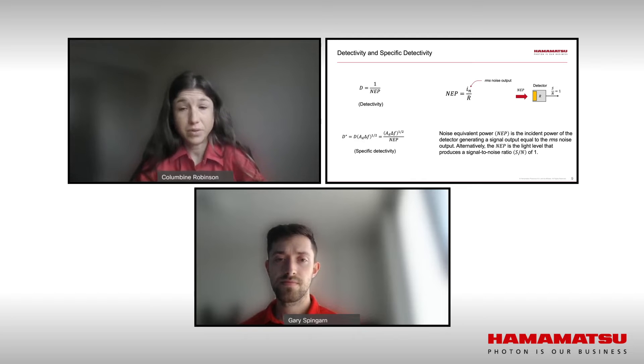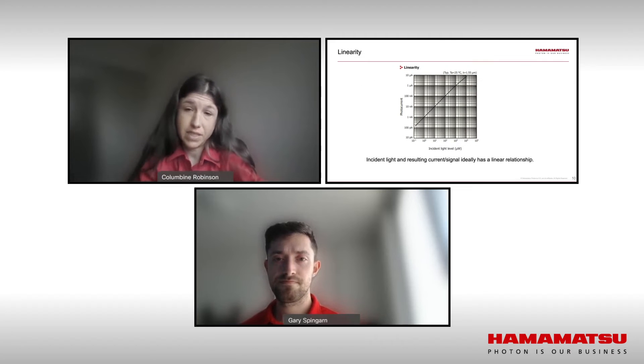NEP is the amount of signal required to achieve a signal-to-noise ratio of one. Ultimately you want as high of a signal-to-noise ratio as possible. D-star is the reciprocal of NEP, so the higher the value, the better. Now for linearity: when looking at the sensitivity of a detector, a certain amount of detected light power will yield a certain amount of signal. Ideally, the relationship between incident power and signal is linear so that no software correction is required and tools can be matched.